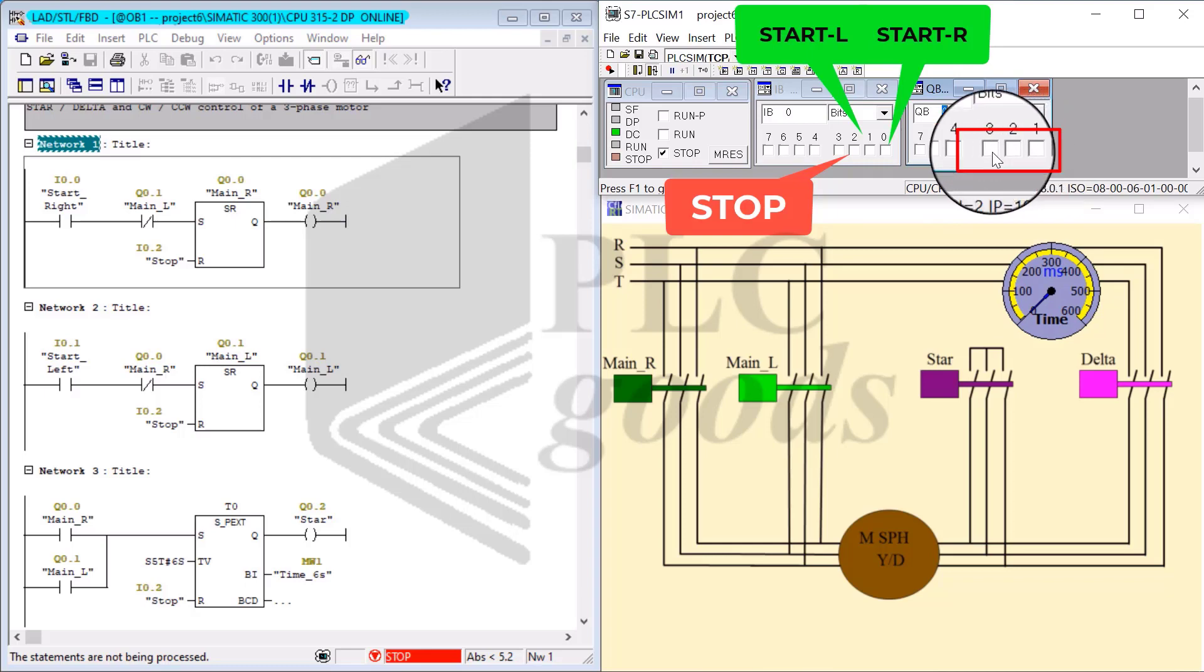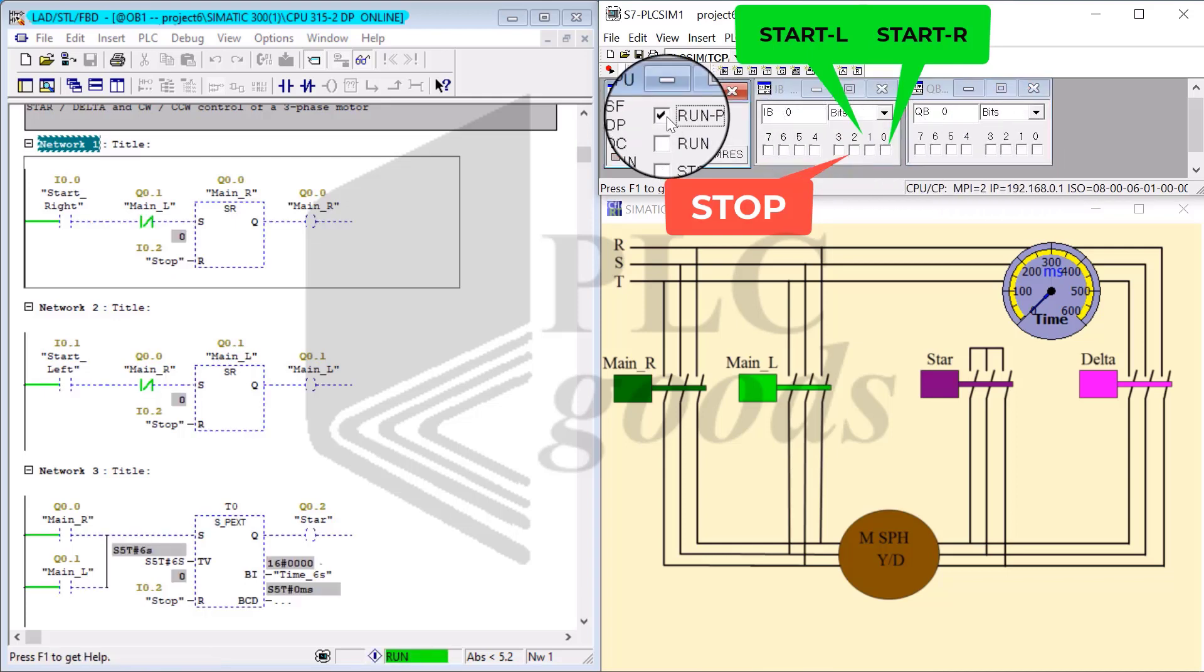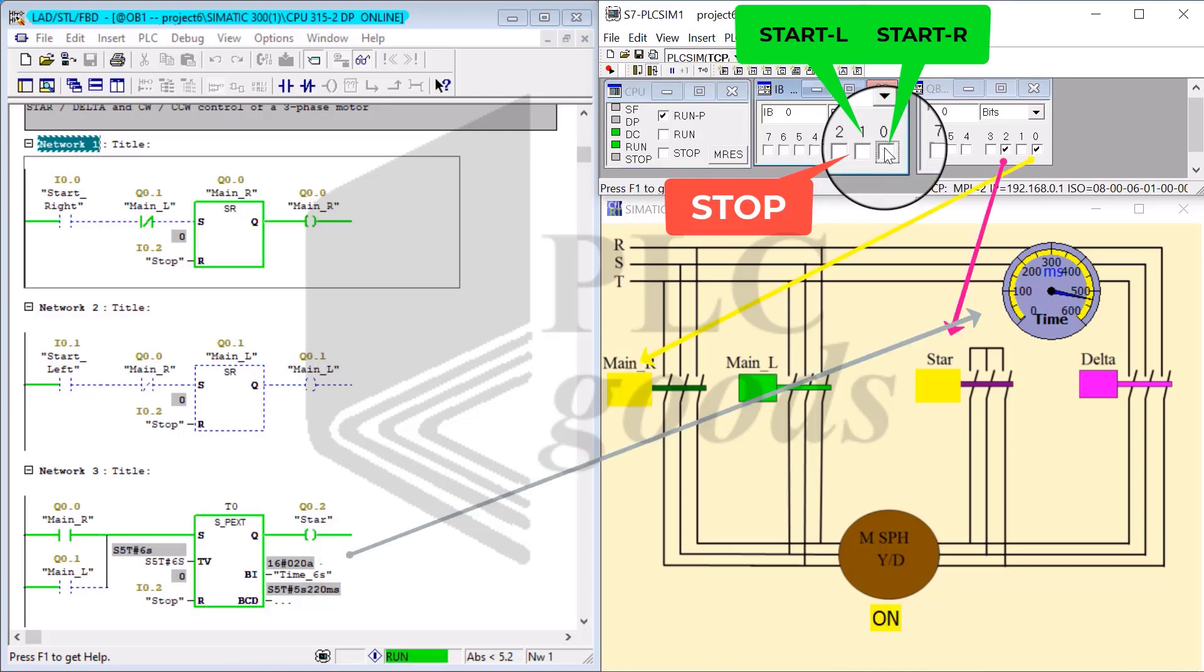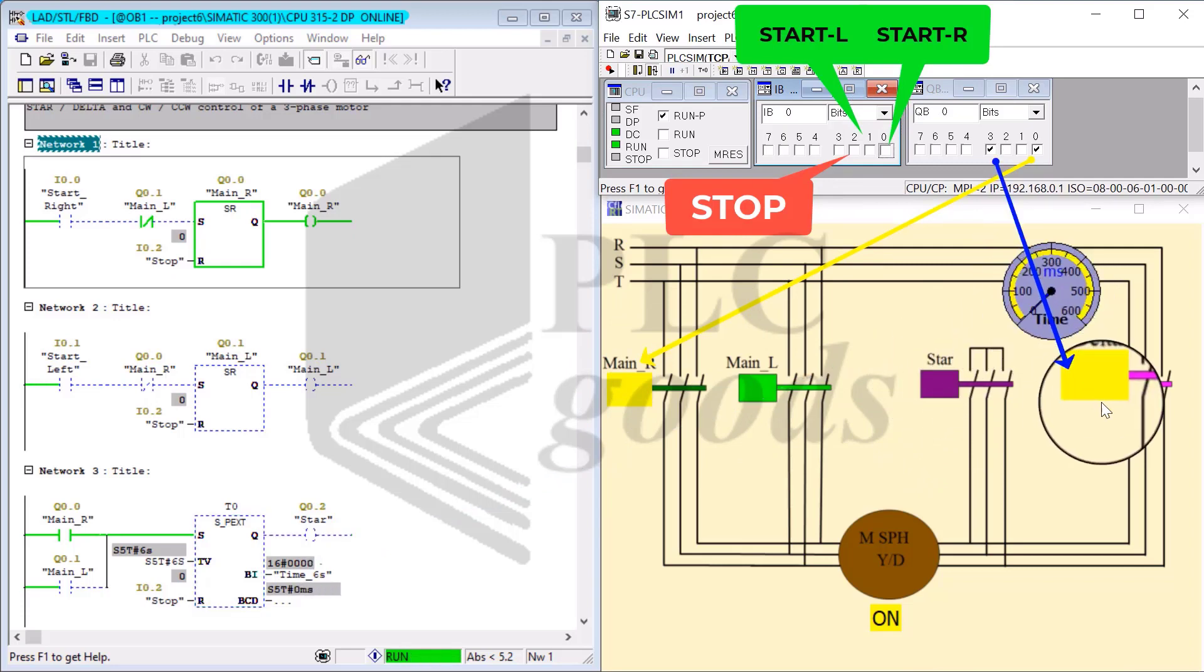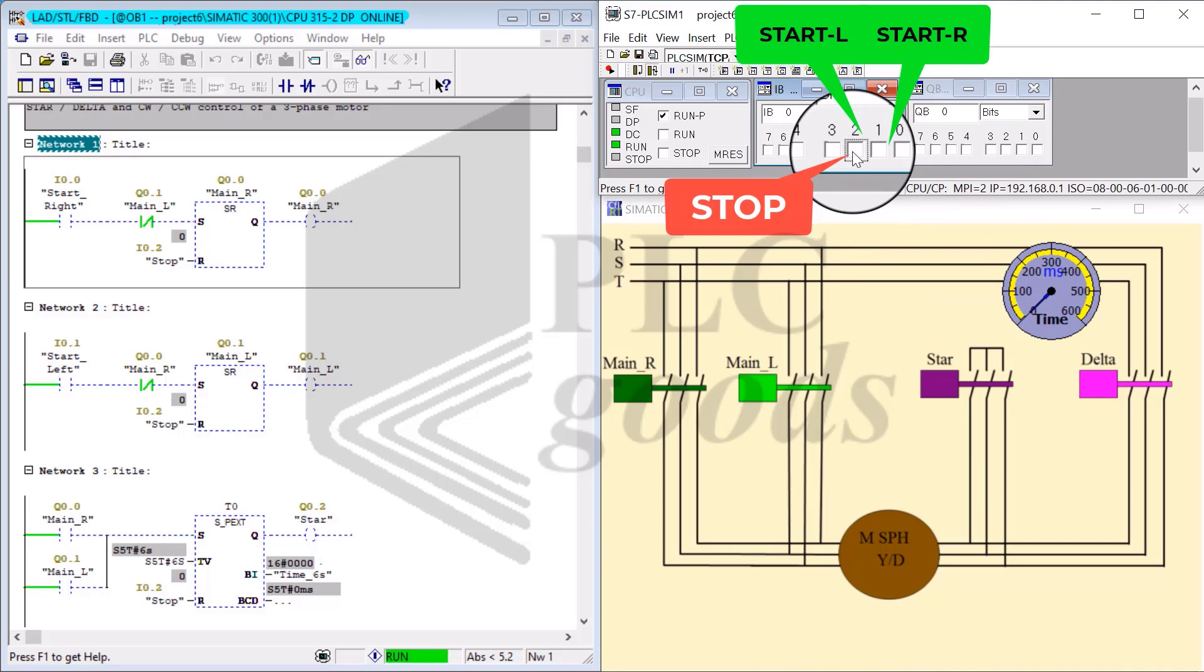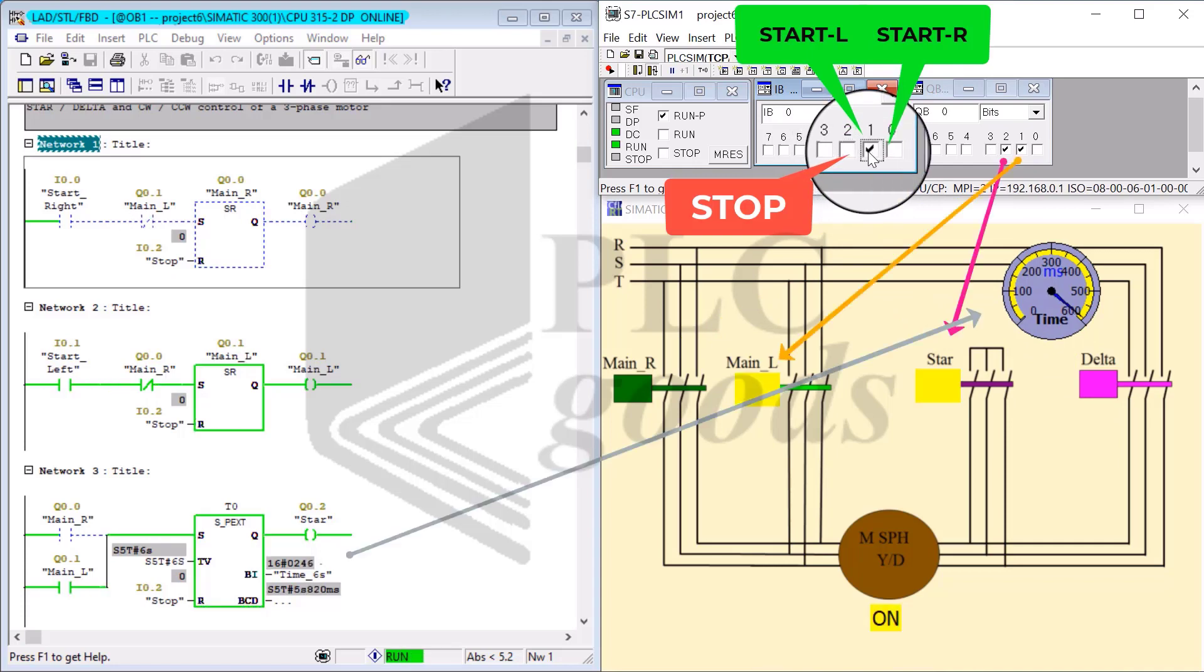I go ahead and turn on the program and tap on the start R. Main R and star first turn on, and after six seconds delta turns on. I go ahead and stop the circuit and tap on the start left. The same happens this time: main left and star turn on, after six seconds delta kicks in.